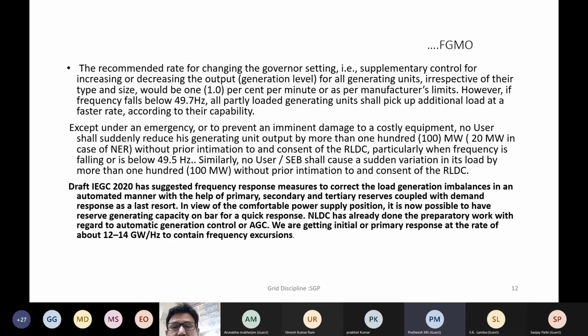Okay, then you said the megawatt should be reduced. Then that doesn't help, right? Megawatt reduction is for the purpose of limitation on the loading of the line. In case, as I said, there is an evacuation limitation because of voltage in the transmission line, then you can reduce the MW generation so that line loading becomes within the capability of the line. So it's not only the capability of the machine, you have to see the capability of the generator transformers and lines also. That's why I said, AVR control, voltage control, and the active power control on governor, they are two independent.